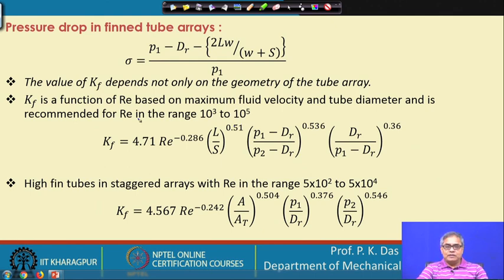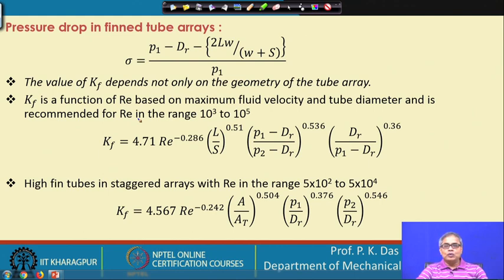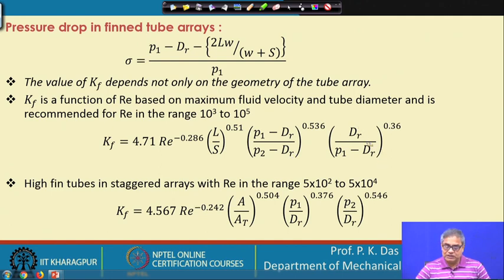Reynolds number Re is specified based on the bare tube diameter and the maximum velocity. It covers the range in which fin tube heat exchangers are generally used. K_f depends on Re raised to some power, and also on the ratio L/s, the pitch, the root diameter, and other geometric parameters. Basically K_f depends on Reynolds number and the diameters of the tube and fins.